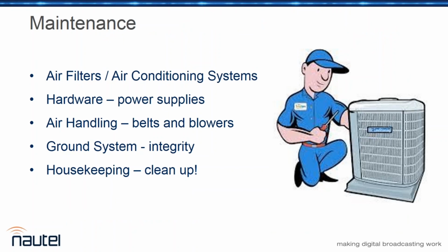Air filters are one of the big things, and air conditioning system maintenance, cleaning out condenser coils, just exercising air conditioning. If you've got a lead-lag system, swap them back and forth so you get the same run time on each. The one thing I don't see here that I really should have is generator testing.